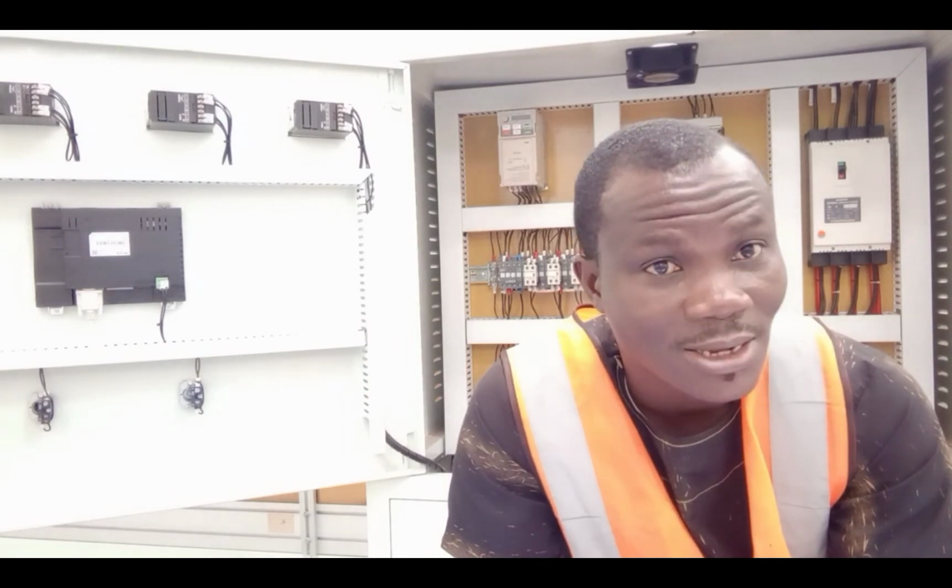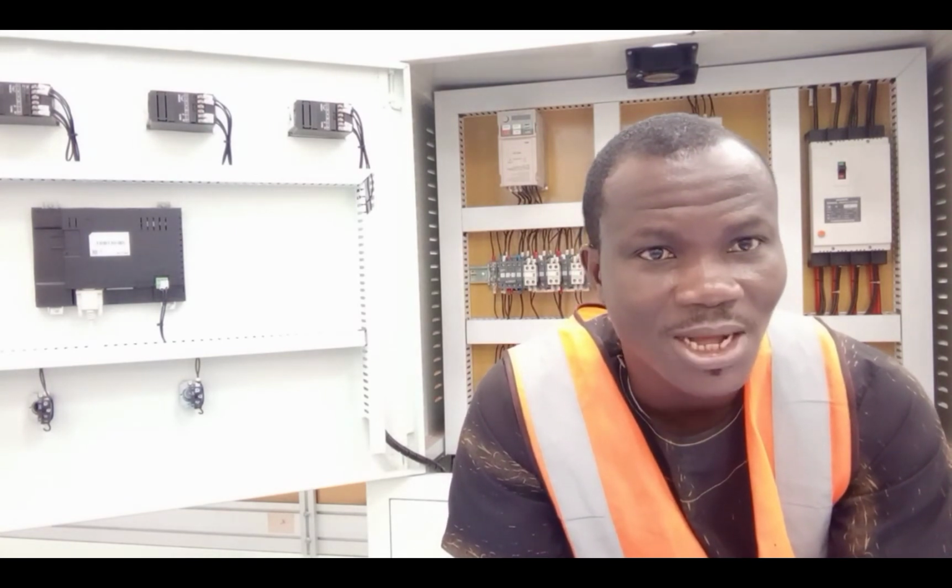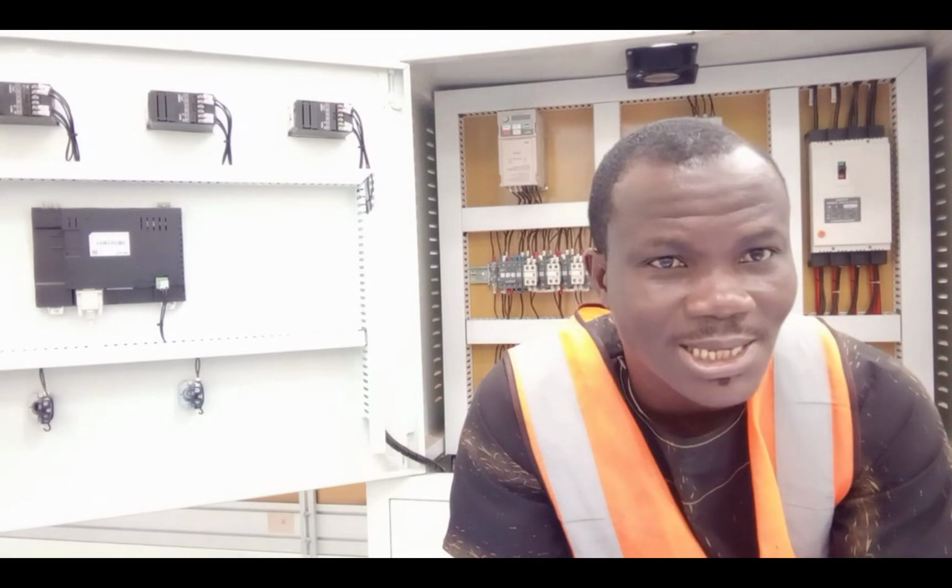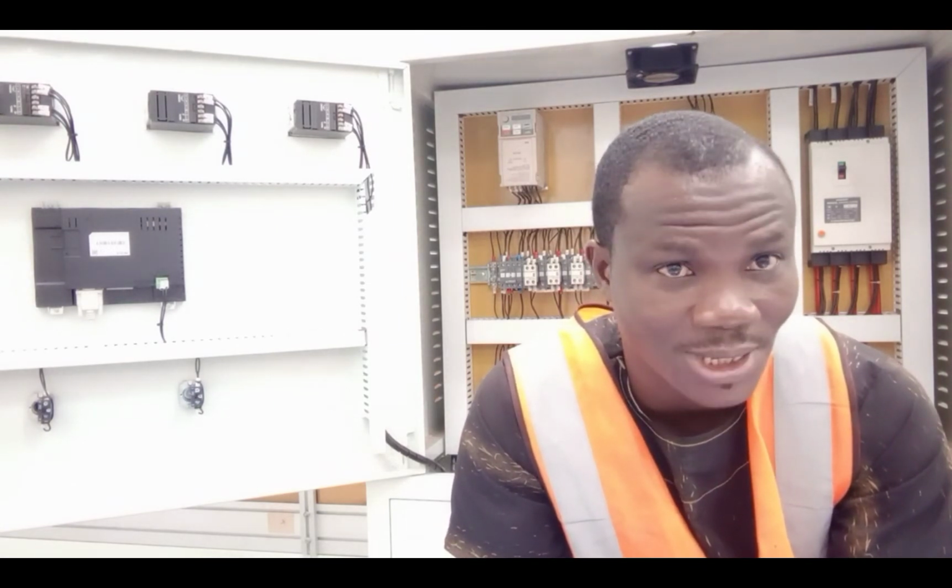Now, if you want to use a 10 amps breaker to protect this circuit, what you are doing is that you are protecting the cables all right, but you are not offering a bit of protection to the loads that you have in the circuit. In order to protect a circuit properly, the circuit breaker should be able to protect the loads that are connected in the wire or in the circuit.